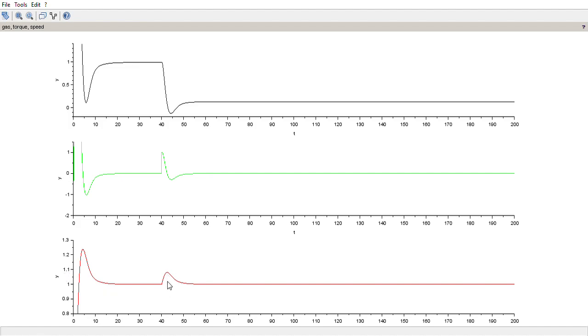So this is from my recollection of working on turbines. This is about what happens on a full load rejection on a frame 5. You have a curve about like this, and so from 40 to, let's say, 55, which is 15 seconds to recover. The highest speed is 110%.